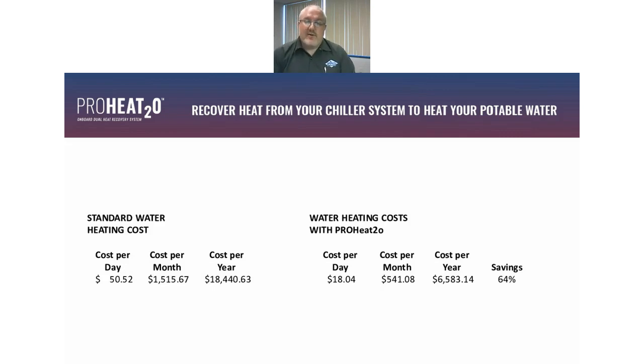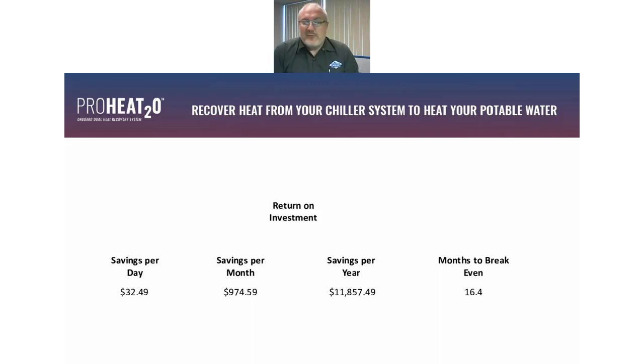And when we add in the ProHeat2O heat recovery system, that cost per day comes down significantly, because we're no longer having to heat from 65 to 180. Now we're able to heat only from 140 to 180. So our cost per year is just a little over $6,500, representing about a 64% savings versus not operating with the heat recovery system. So at the end of the day, we're looking at a total return on investment on the system of just a little over a year, 16.4 months, just to get the cost of that investment back. So that is a pretty good return on investment for a piece of equipment, and I think it really makes heat recovery a justifiable scenario to explore inside the brewery.